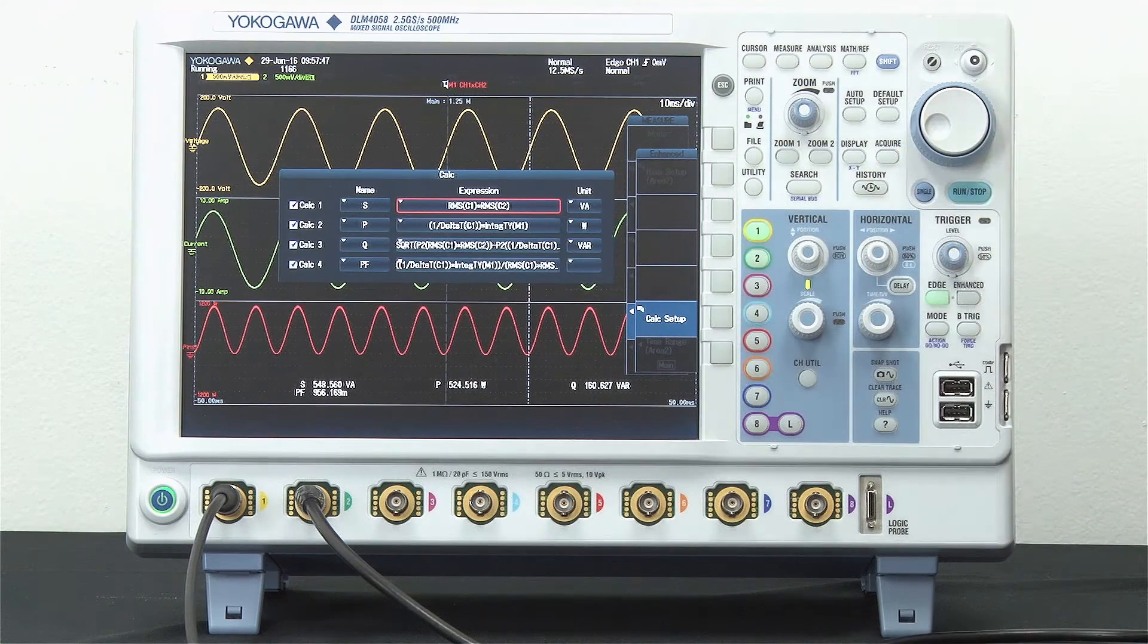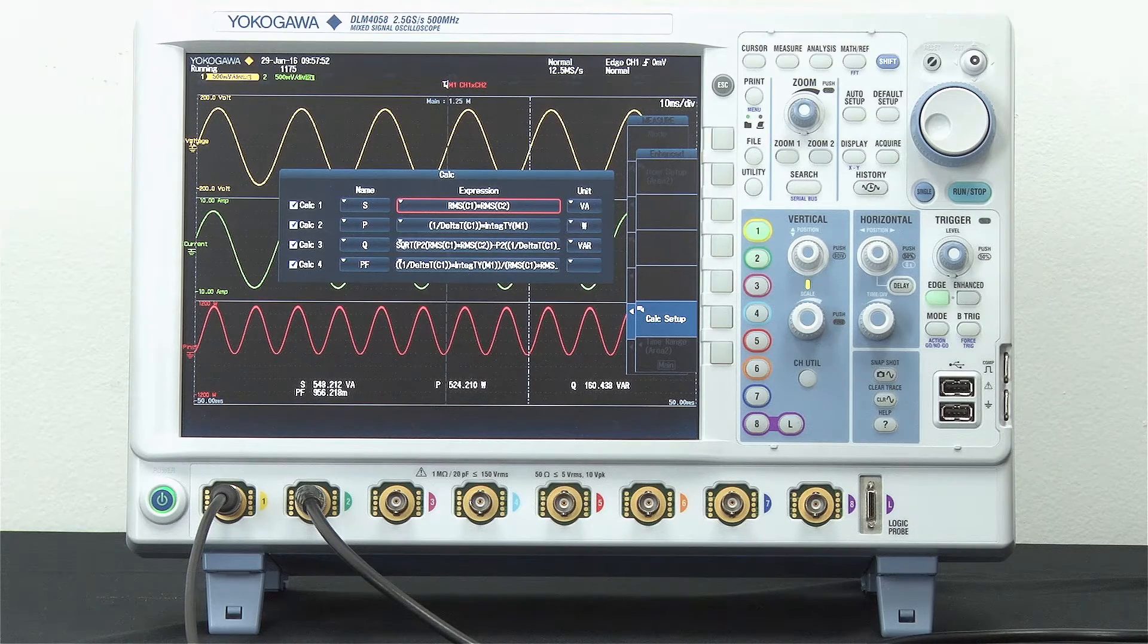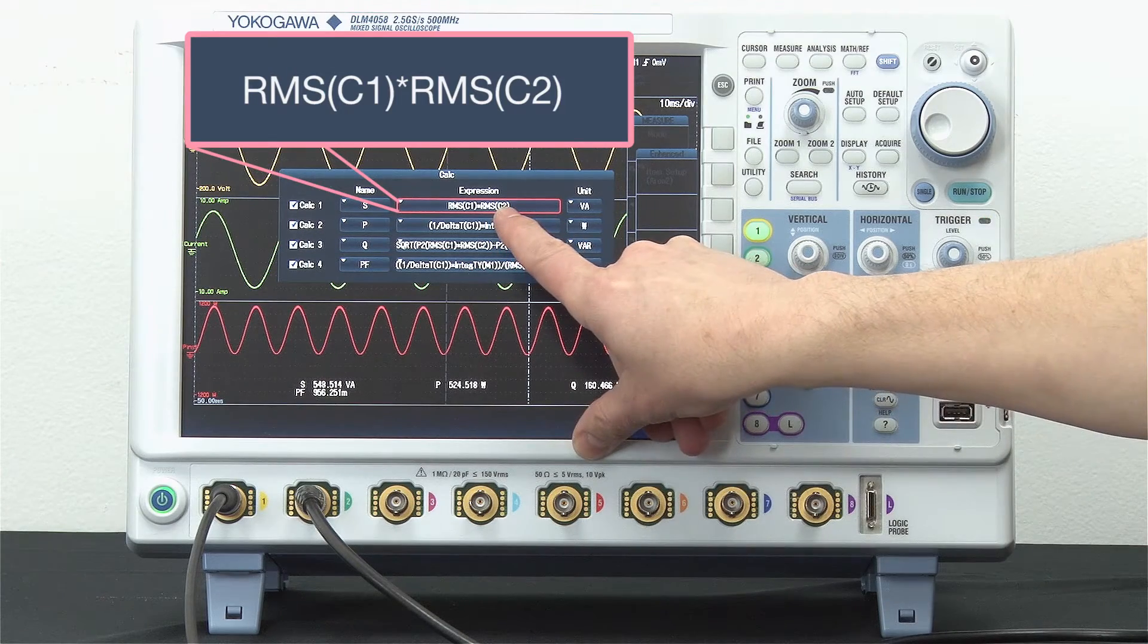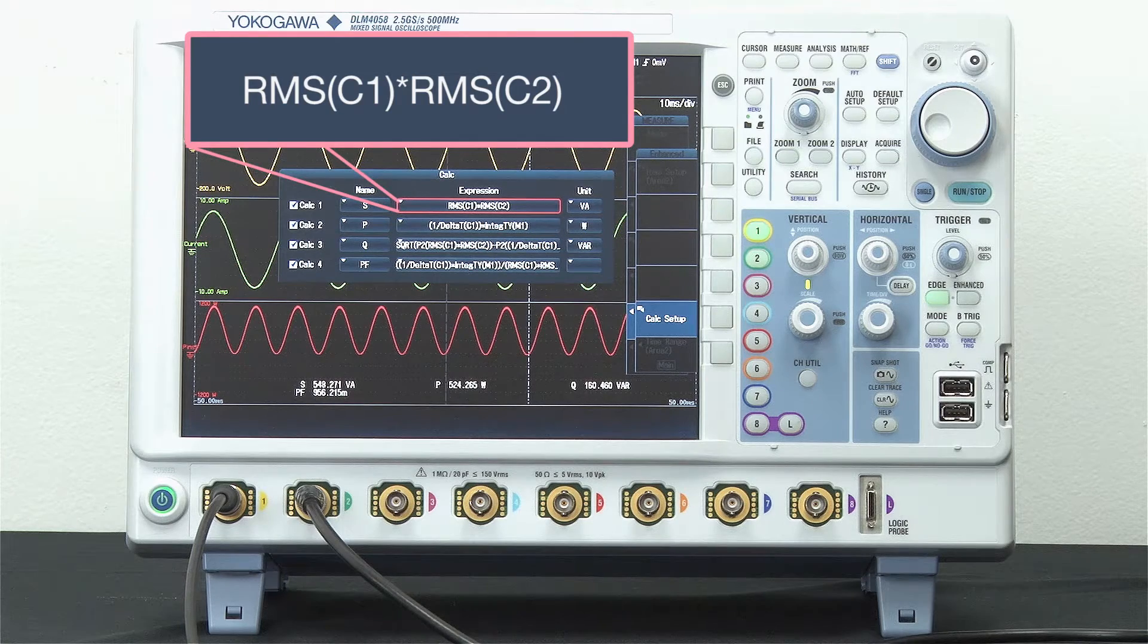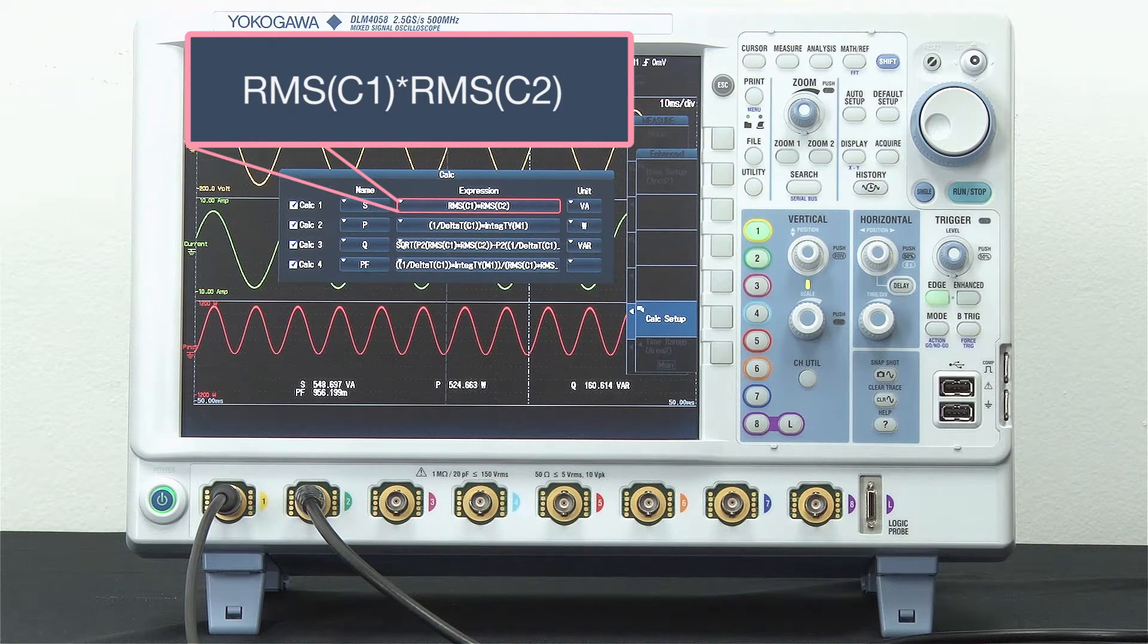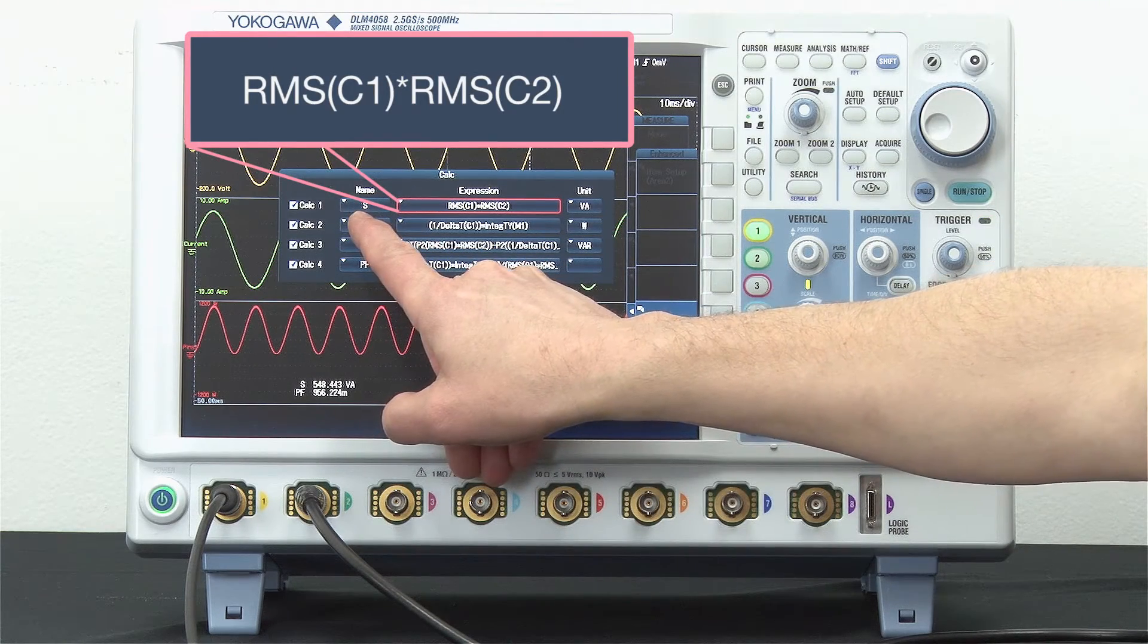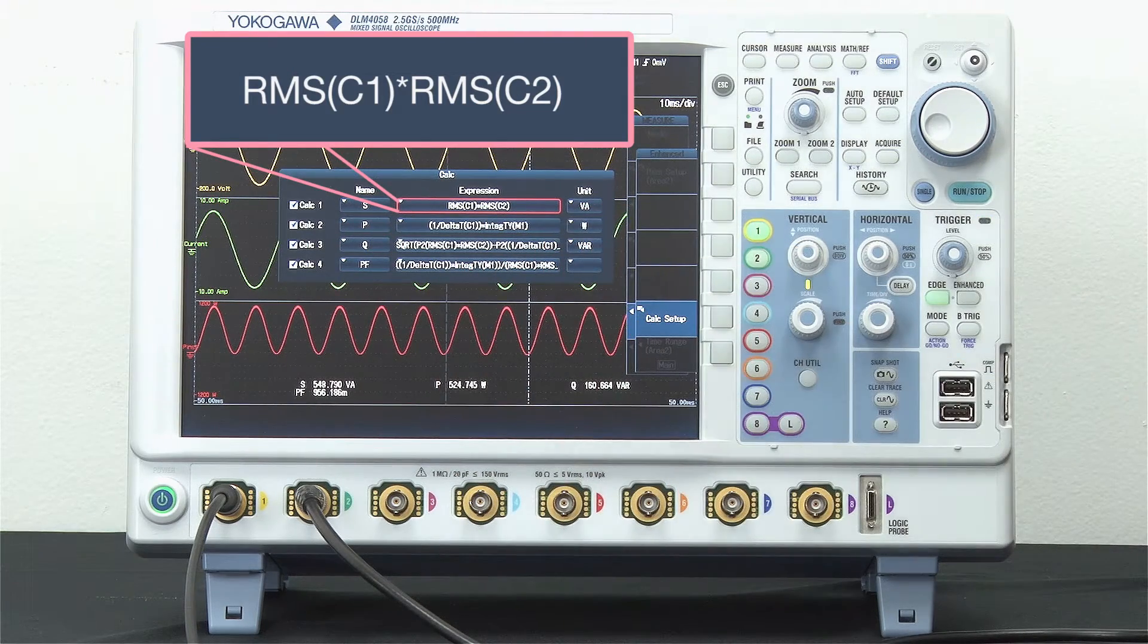To enter these equations, I use either the soft key onboard editor or I can use an external USB keyboard. Here you can see that I've built the equation for apparent power. The equation I've put in calc one field is the equation for apparent power, which is the RMS of the voltage waveform times the RMS of the current waveform. I've named it S, which is an industry standard for apparent power. I've given it units of volt amps, also industry standard units.